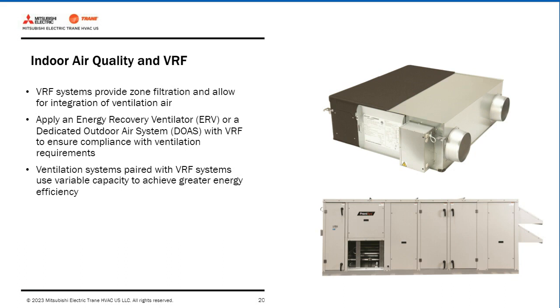Outdoor air units combine ERV and DOAS capabilities to condition 100% of the ventilation load. They connect directly to a VRF condensing unit like an indoor unit that are purpose-built for zoned ventilation. Outdoor air units are useful in facilities with diverse ventilation requirements. We've got a lot of different solutions to employ the variable compressor options to get the best efficiency.